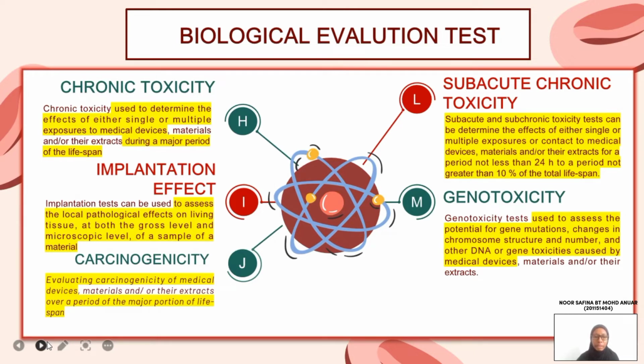of the lifespan. Implantation effect can be used to assess the local pathological effects on living tissue at both the gross level and microscopic level of a sample of a material. Carcinogenicity: evaluating carcinogenicity of medical devices over a period of the major portion of lifespan.